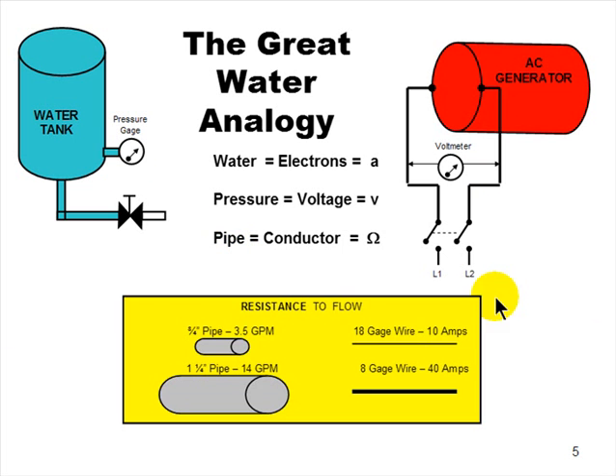Okay? Now, if you're working with a boiler at 20-pound pressure and you've got a 3/4 inch pipe, at proper velocity you're going to handle about 3.5 gallons of water a minute. That's all you can get through that pipe at the proper feet per second velocity you want. Now, if you want to increase flow, you've got to make the pipe bigger. If you want 4 times the flow, going from 3.5 to 14 gallons a minute, you need a bigger pipe for the same pressure and the same temperature and so forth. It's the same here.